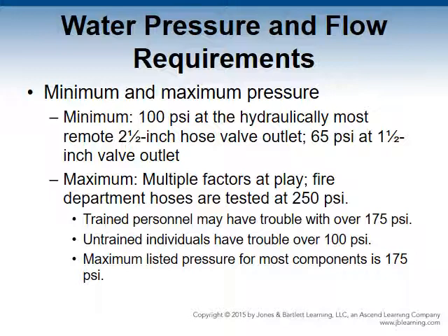The maximum listed pressure for most components is 175 psi. If the pressure is exceeded, pressure control devices must be installed.